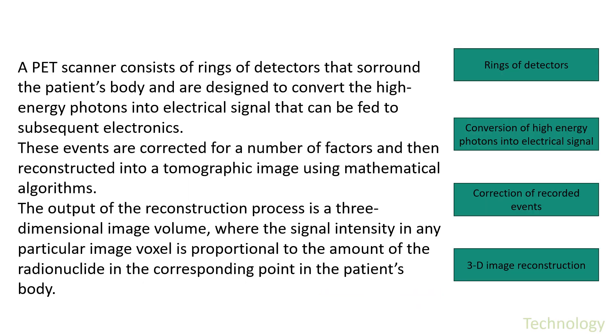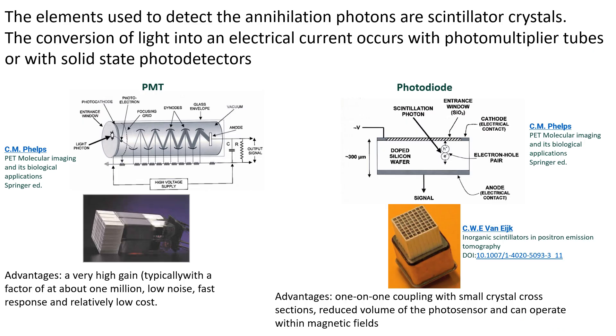A PET scanner consists of rings of detectors that surround the patient body and are designed to convert the high-energy photons into electrical signals that are fed to subsequent electronics. These events are corrected for a number of factors and then reconstructed into a tomographic image using mathematical algorithms. The output of the reconstruction process is a three-dimensional image volume where the signal intensity in any particular voxel is proportional to the amount of the radionuclide in the corresponding point of the patient body. The elements used to detect the annihilation photons are scintillator crystals, whose properties will be described later in this presentation.